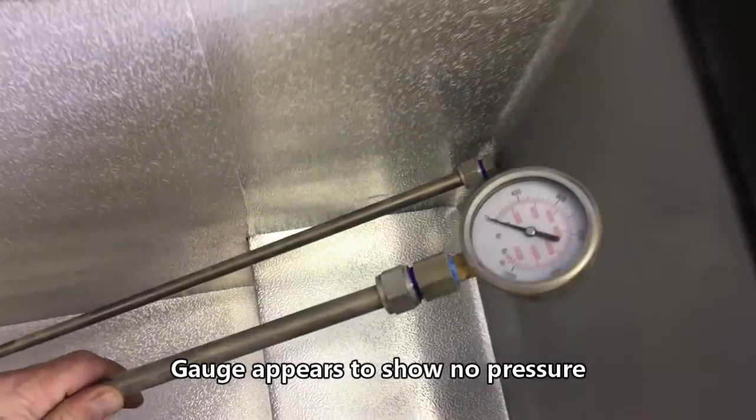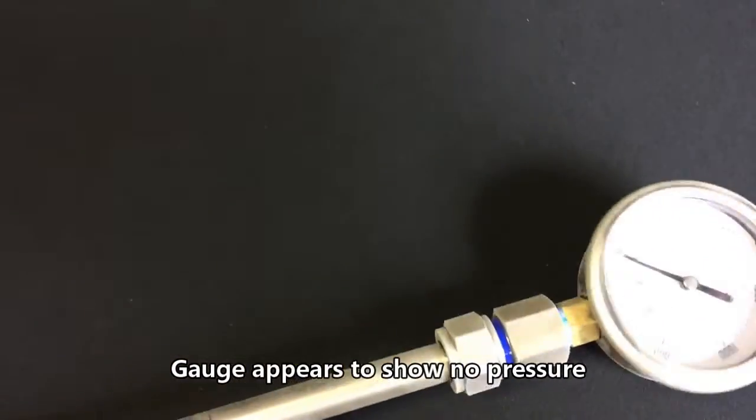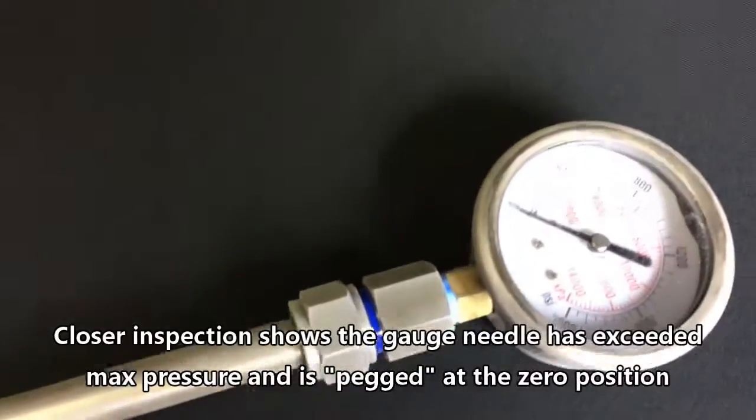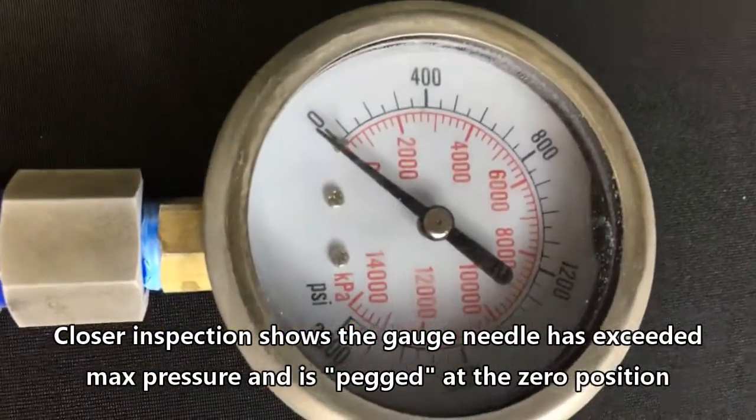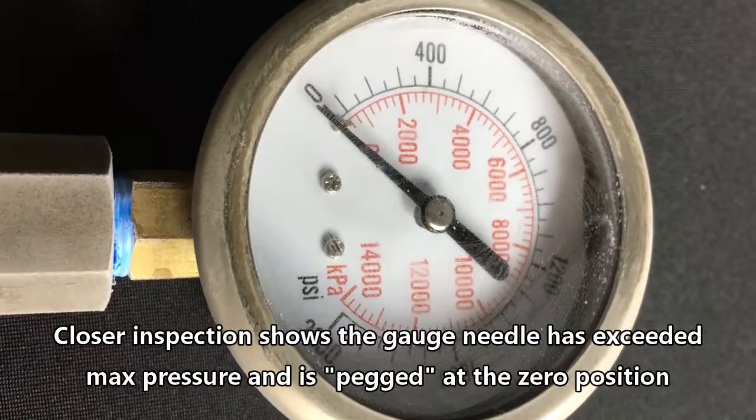Test sample number three appears to show it is no longer holding pressure. Upon closer inspection, the gauge needle has exceeded max pressure and is pegged at the zero position. After thawing, the gauge returns to 1,200 PSI showing no pressure leakage in the sample.